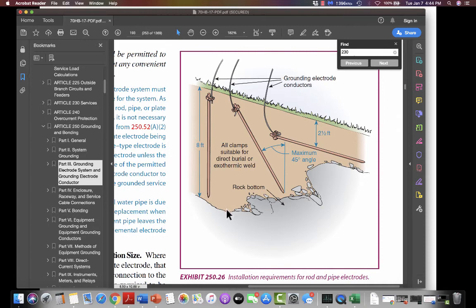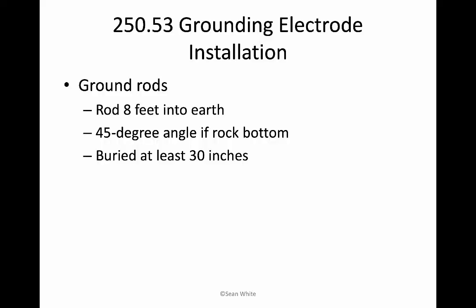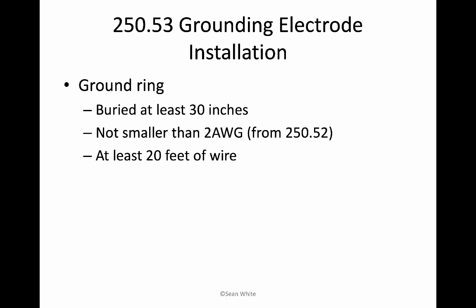However, if you start hitting rocks, you can go at an angle. And if that doesn't even work, you can just dig a hole 2.5 feet down and go sideways. And 2.5 feet just happens to be 30 inches. What a coincidence. Ground rings.